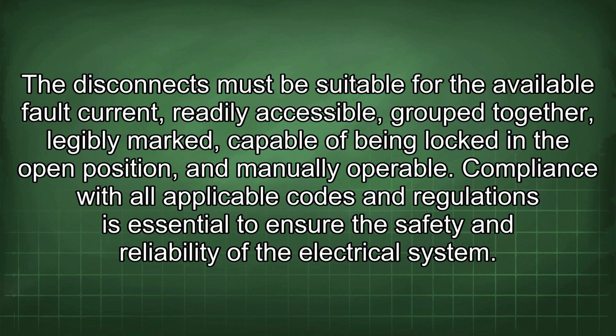The disconnects must be suitable for the available fault current, readily accessible, grouped together, legibly marked, capable of being locked in the open position, and manually operable. Compliance with all applicable codes and regulations is essential to ensure the safety and reliability of the electrical system.